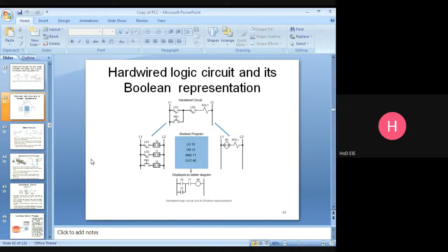This one is for the seal-in contact. Already I discussed it. Normally, the stop push button is in closed condition and the start push button is in open condition. Once this one is closed, this one is a momentarily closed switch, closed and opened. Once this one is closed, at that instant itself, the motor starter coil will be energized and keep energizing. Even though this one is opened, the motor starter coil will be kept energized. Understand? This kind of circuit we call a seal-in contact circuit or holding circuit. Pasupati, is it okay? Yes, sir.